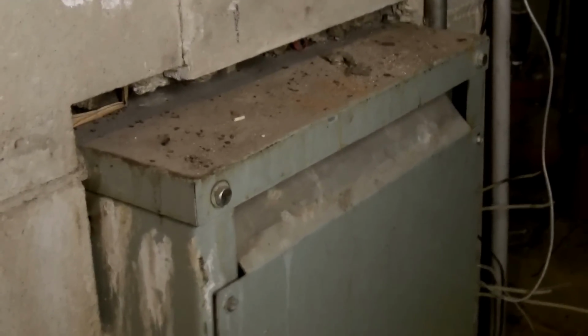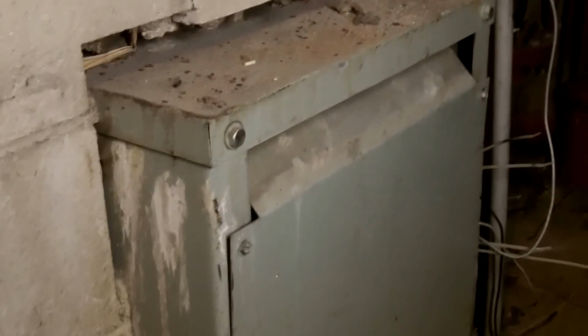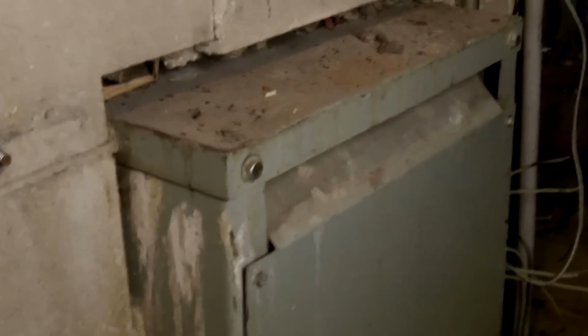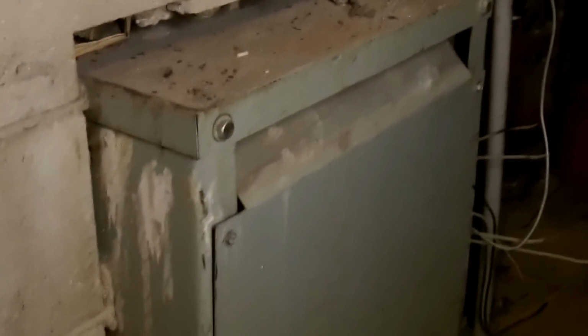I'm taking a look at the ventilation of this transformer, and as you can see, this transformer has been recessed into the wall, which means the ventilation openings in the back on the bottom here and the openings on the back side at the top are going to be obstructed by the wall, so this transformer is not going to be able to be cooled properly.